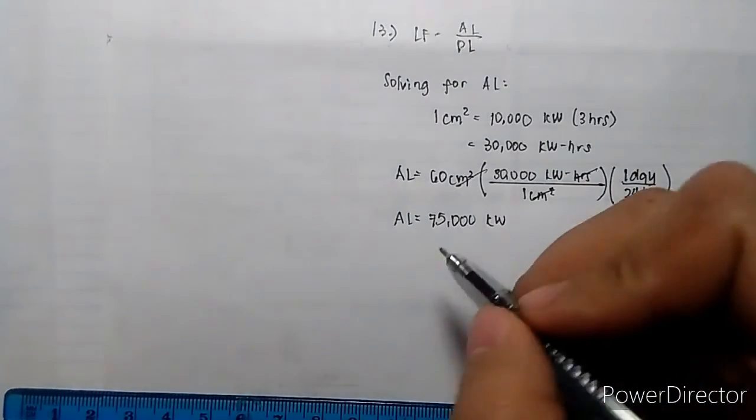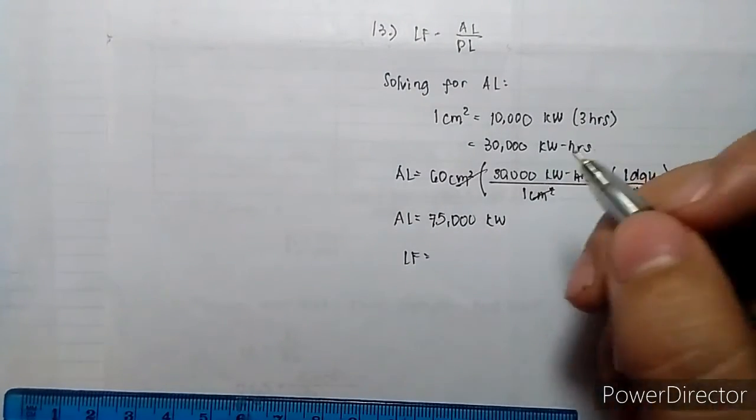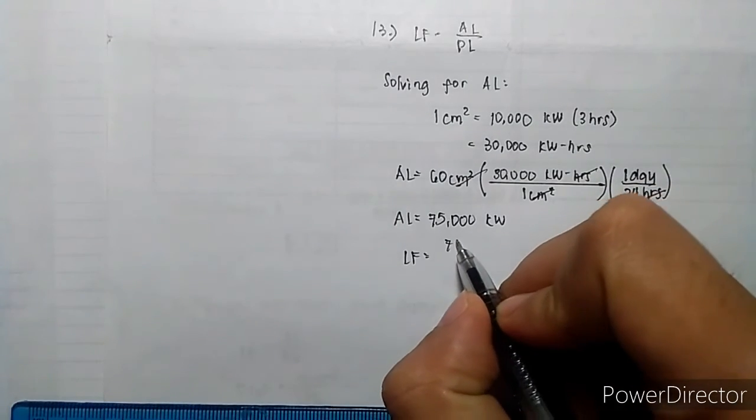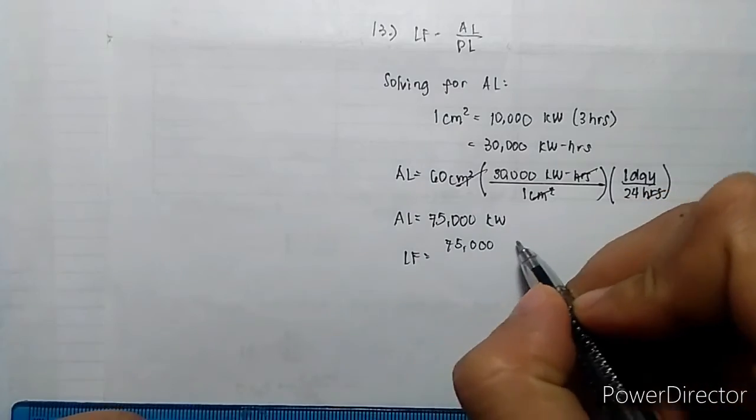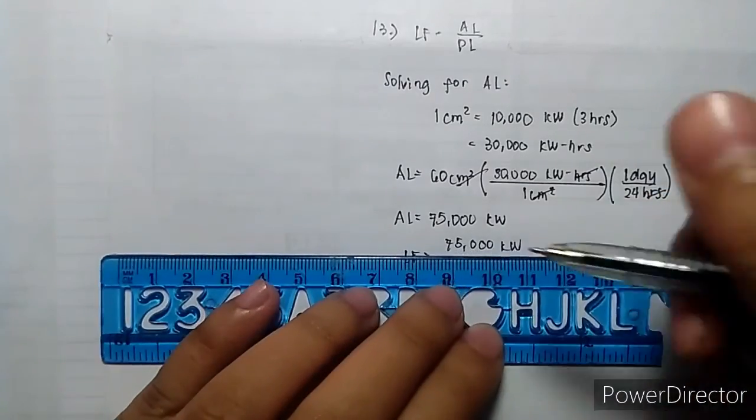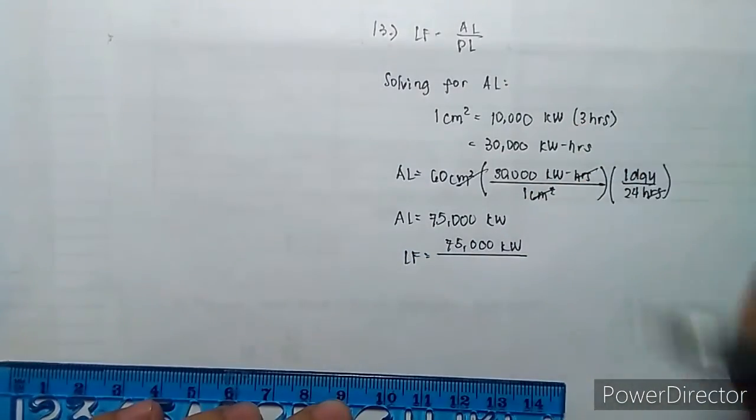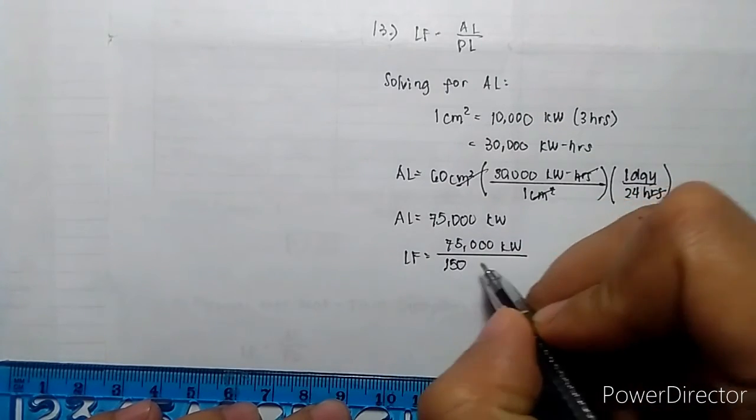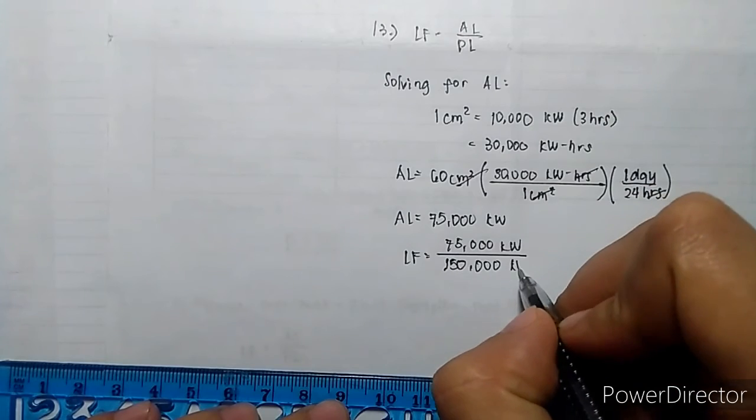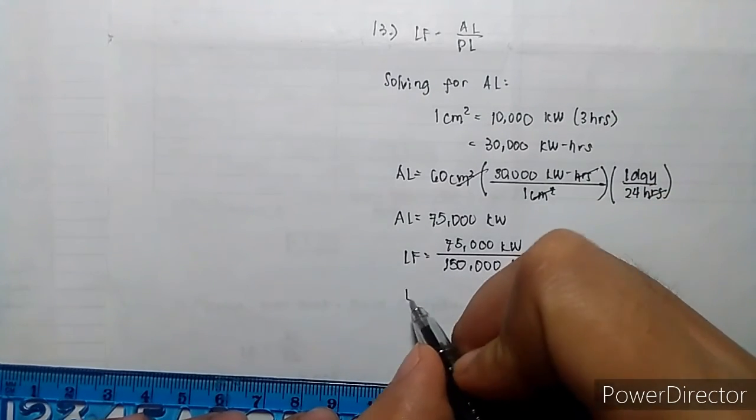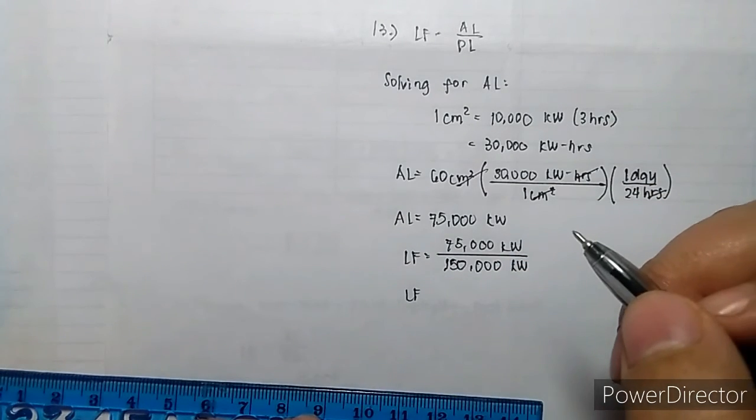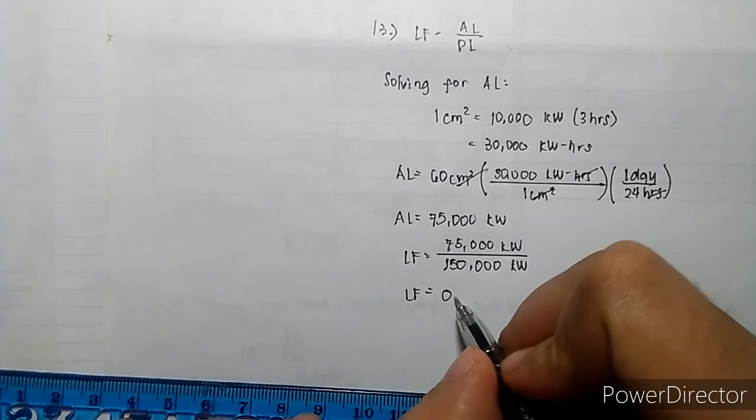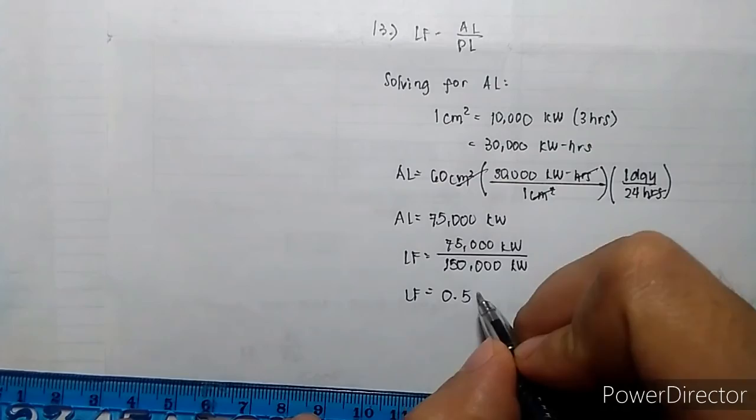Solving for the load factor is equal to the average load of 75,000 kilowatts over the peak load of 150,000 kilowatts. The load factor based on the 15 minute peak is equal to 0.50.